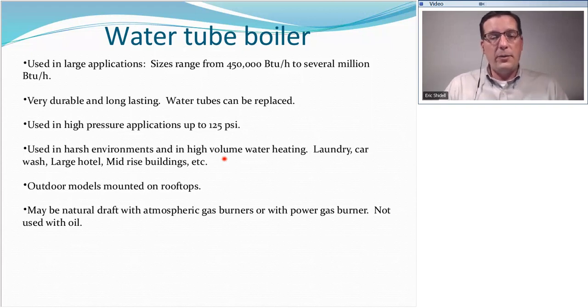We're frequently going to find water tube boilers used in harsh environments where we may have contaminated combustion air, for example, or chemicals are being used in the vicinity of the boiler because these thick metal tubes can tolerate that. They can handle it without being rusted through. We're also going to use them in high volume water heating applications, sometimes like laundries, commercial laundries, commercial car washes, large hotels with lots of domestic water usage, older mid-rise buildings. We're talking buildings built prior to 1970 is where we're going to see a lot of these.